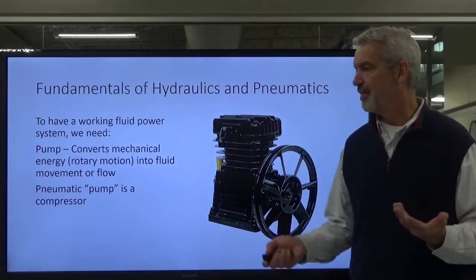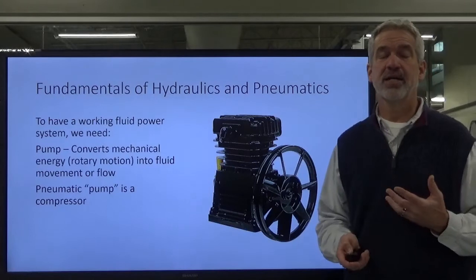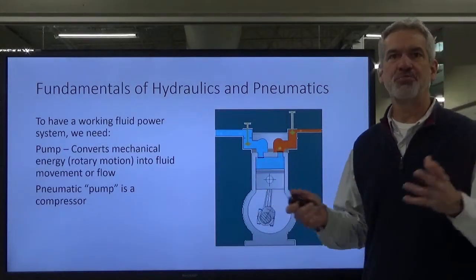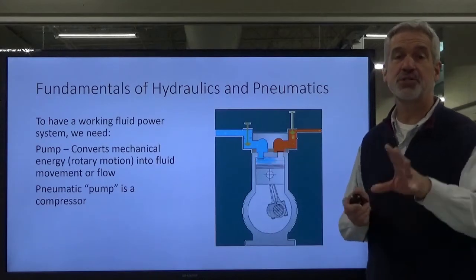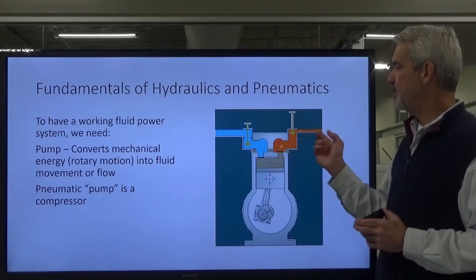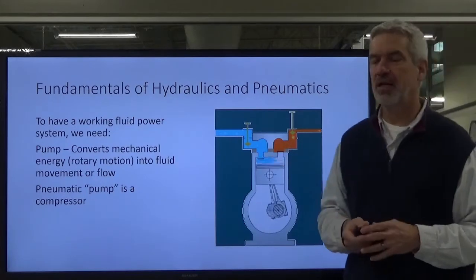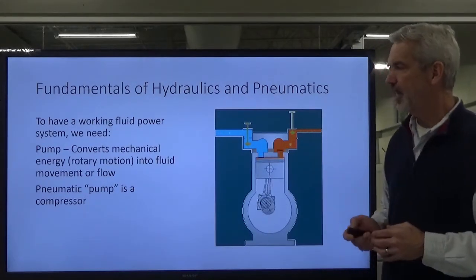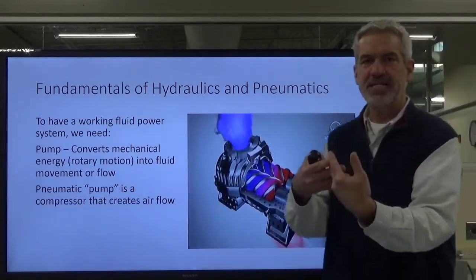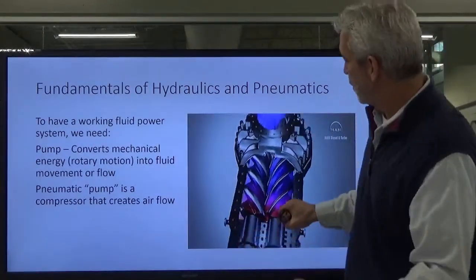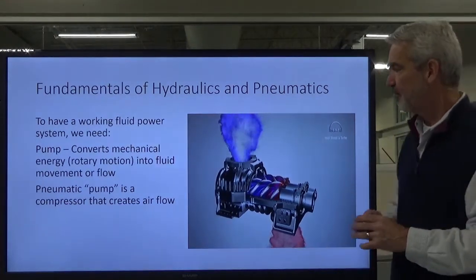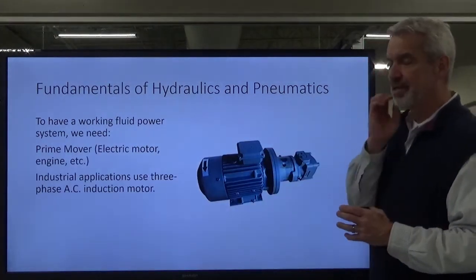With compressor, we talked about it is the pump as well, but you will not see that on a schematic. But this is a reciprocating air compressor right here that you'll typically see if you buy a compressor at Home Depot or Lowe's. It's reciprocating, unless it's a screw-type compressor. It pulls air in, closes the valve off, and then exhausts it to our system out here. These valves are back and forth, open and closing, and allowing it to compress on the hot side over here. This is a screw-type compressor as opposed to the reciprocating, pulling air in here. These very, very tight machined screws, the air gets pulled in there and gets compressed and compressed and pressed tighter and tighter until it comes out. That is a screw compressor.